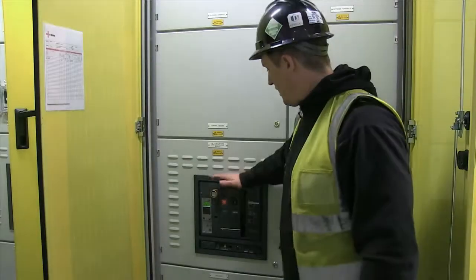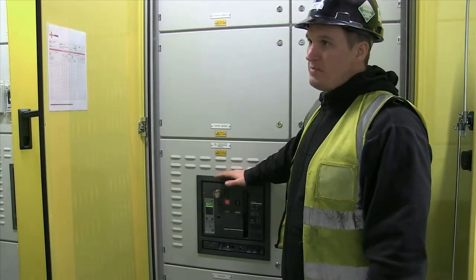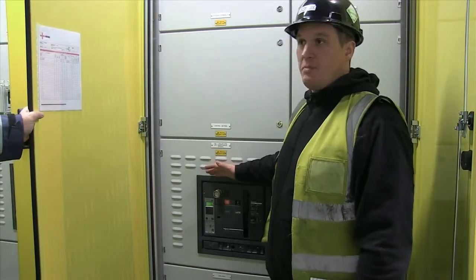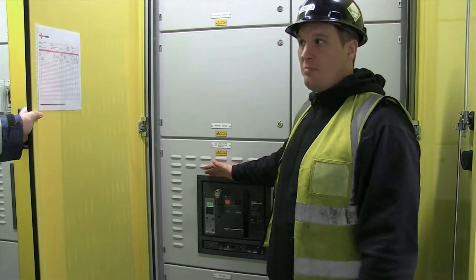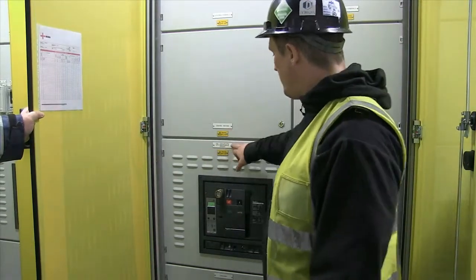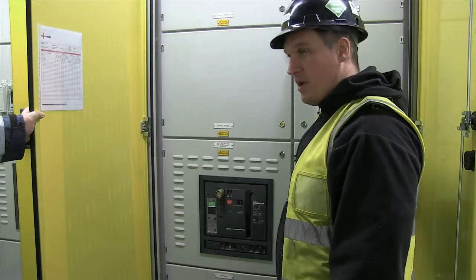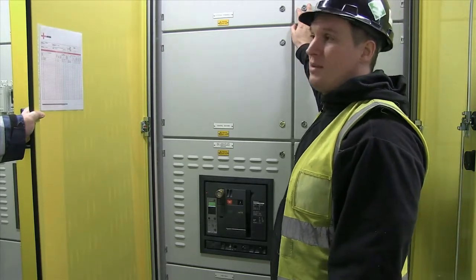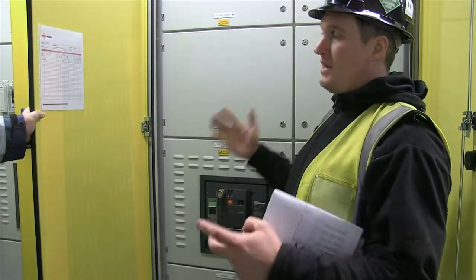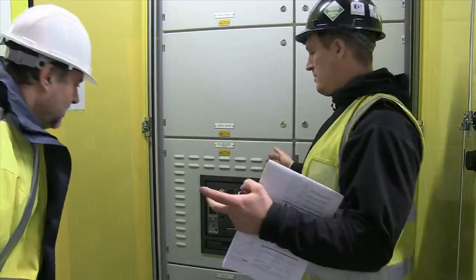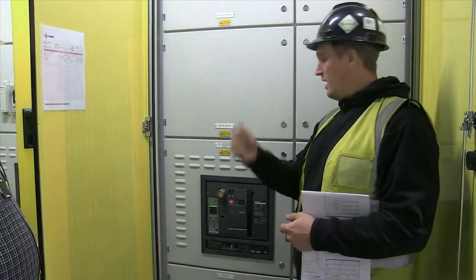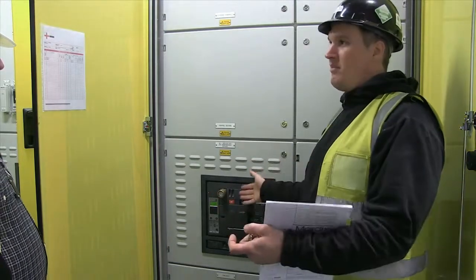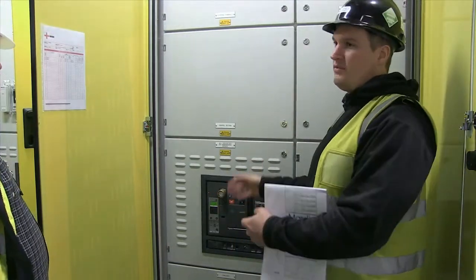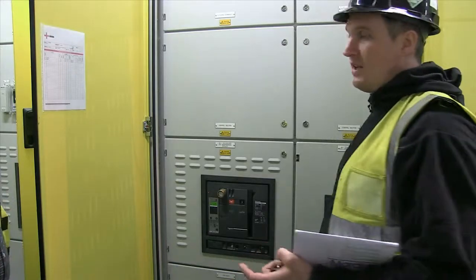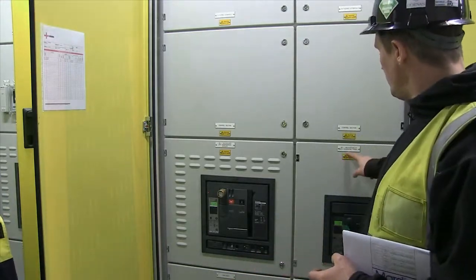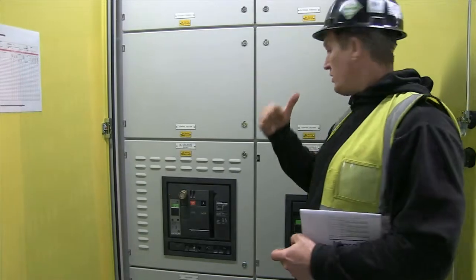Now this is a maintenance bypass, UPS maintenance bypass. I'm not going to go through the procedure because I know that Socomec are going to go through it with you. But basically what happens is you have a maintenance bypass here, you have a static bypass over at the UPS's. When he puts it into static bypass, you can parallel the main supply, because static is a main supply and this is a main supply. You can parallel them up, give you the key, will go into there, you can then parallel them up, go and turn the UPS's off, and you've not lost the mains. But I do know that he's going to do that. And then this supplies the essential panel, which is just around the back, which will go there in 2 seconds.